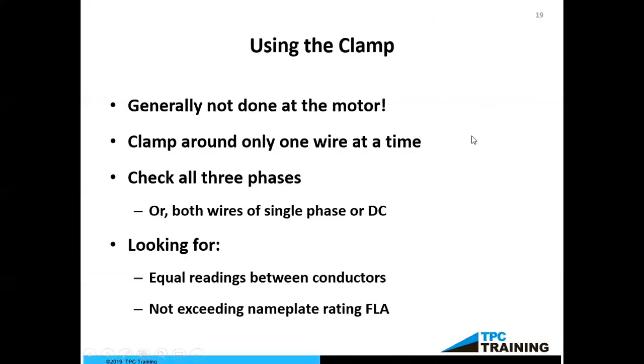So then back here, a few slides when I had my meters up there, I was showing you the T5600 that sort of had a fork on it, which is where I could measure current. So sometimes we call that an amp clamp. That one had that fork. I just stick the wire in between those two protrusions on the meter. But a lot of them have an amp clamp, and that's going to give us some great information that we have power on the motor's turning. Maybe the motor's being fed from a disconnect switch or a motor control center. But what I can do on the load side of that disconnect or on the load side of that motor starter in an MCC, I can clamp around each one of those phases.